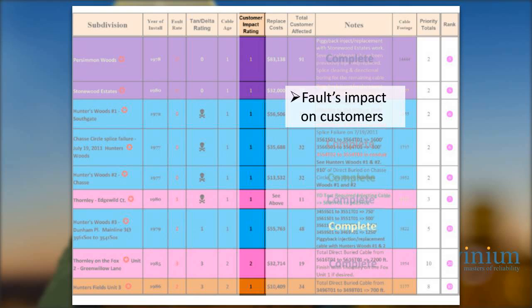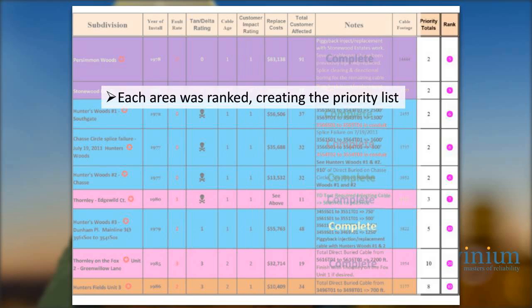What is a heavy piece is the fault's impact on customers. Is it a radial location that's going to be a long sustained outage where we have to dig up and splice? Or are we talking about a loop with 20 single-phase transformers on it? That's going to be much more impactful in terms of customers and SAIDI compared to a 3-transformer loop. So Steve goes through and identifies within the subdivision whether a failure would be more impactful.